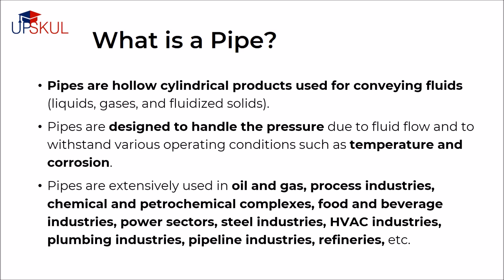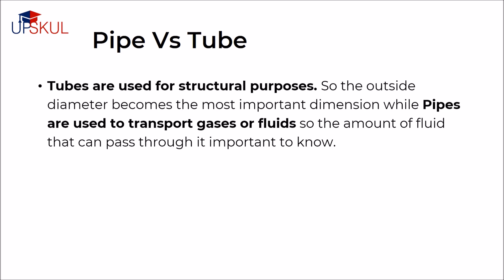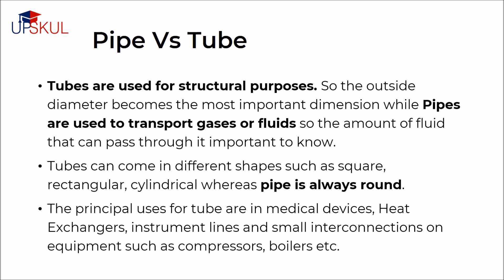In normal life, we might use the terms pipe and tube interchangeably, but in engineering and industry, the terms are uniquely defined. Tubes are used for structural purposes, so the outside diameter becomes the most important dimension, while pipes are used to transport gases or liquids, so the amount of fluid that can pass through it is more important. Tubes can come in different shapes such as square, rectangle, and cylindrical, whereas pipe is always round. The principal uses for tubes are in medical devices, heat exchangers, instrument lines and small interconnections on equipment such as compressors and boilers.